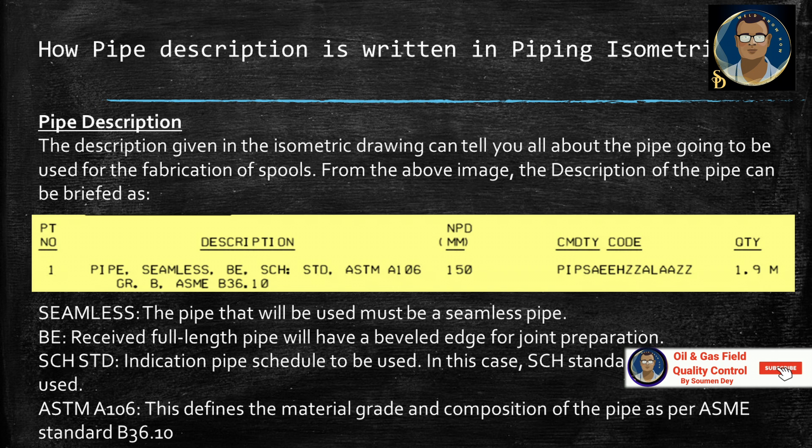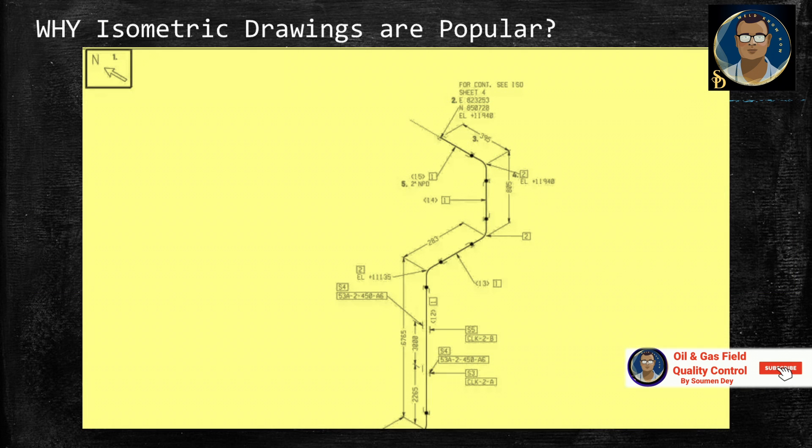Let us have the description: Seamless means the pipe that will be used must be a seamless pipe. BE means received full length pipe will have a beveled edge for joint preparation. Schedule standard means the pipe schedule to be used, in this case is standard schedule. ASTM A106 defines the material grade and composition of the pipe as per ASME standard B36.10.